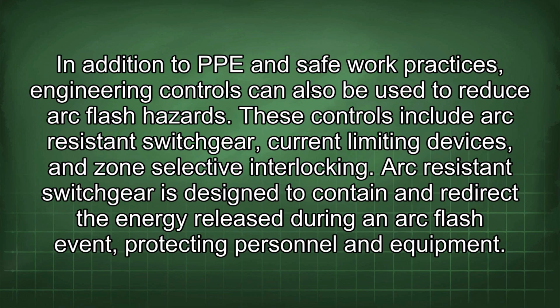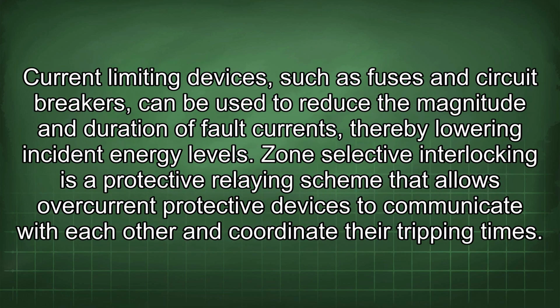In addition to PPE and safe work practices, engineering controls can also be used to reduce arc flash hazards. These controls include arc-resistant switchgear, current-limiting devices, and zone-selective interlocking. Arc-resistant switchgear is designed to contain and redirect the energy released during an arc flash event, protecting personnel and equipment. Current-limiting devices such as fuses and circuit breakers can be used to reduce the magnitude and duration of fault currents, thereby lowering incident energy levels.